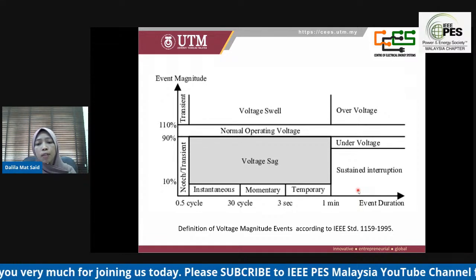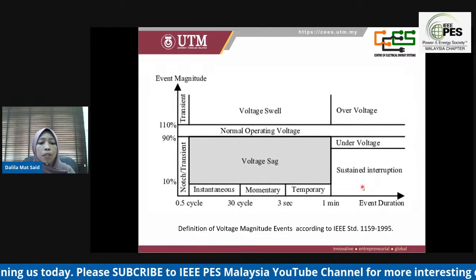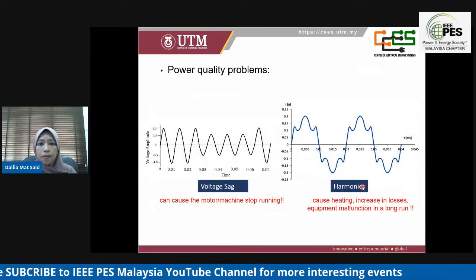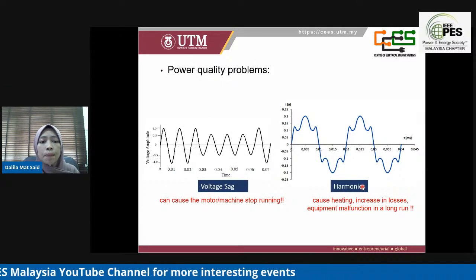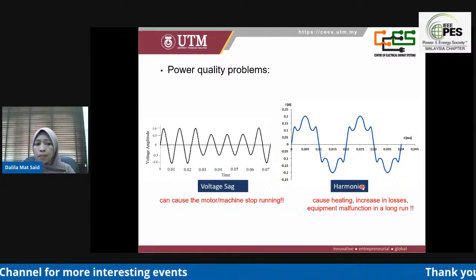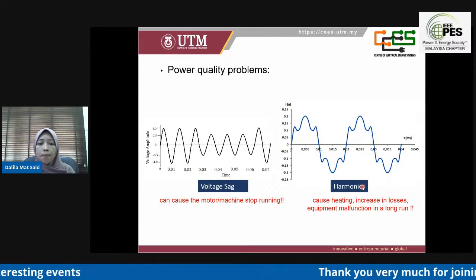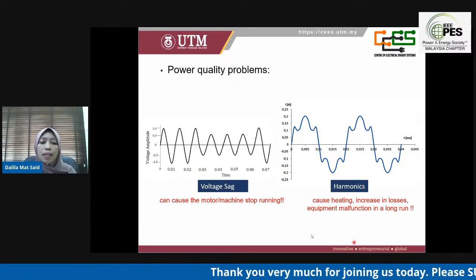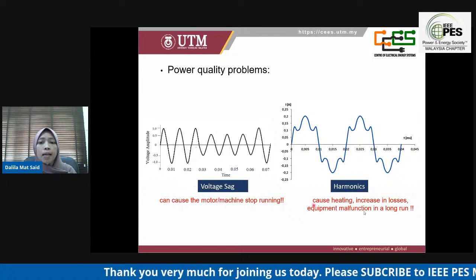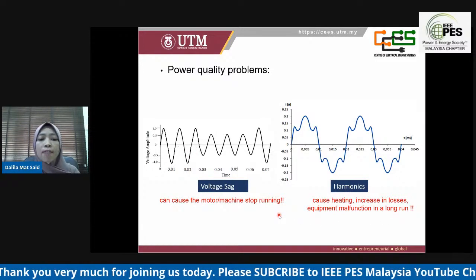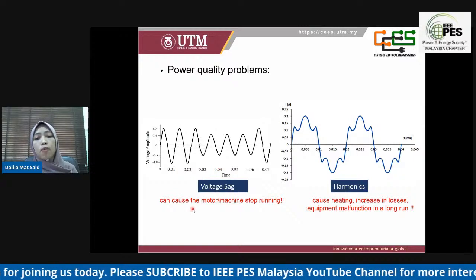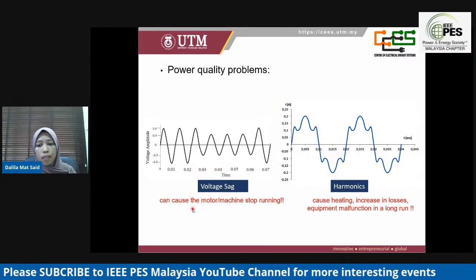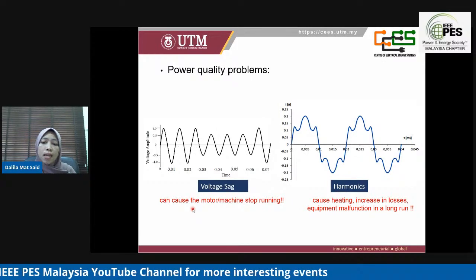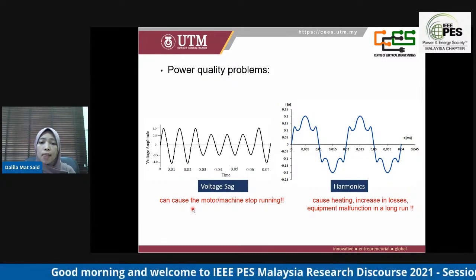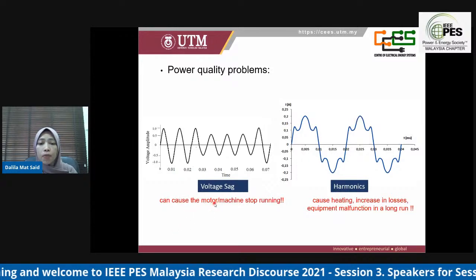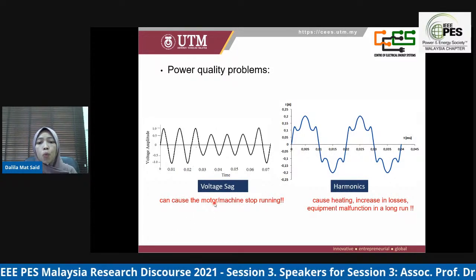However, not all the events or deviations may impact the operation of the machine or equipment. So, from the most common power quality problems, I select 2 most common types in the power system, which are the voltage sags and harmonics. Okay. On the left side is voltage sag. Actually, voltage sag is a decrease of the normal voltage level between 10 and 90% of the nominal voltage at the power frequency for a duration of half cycle to 1 minute.